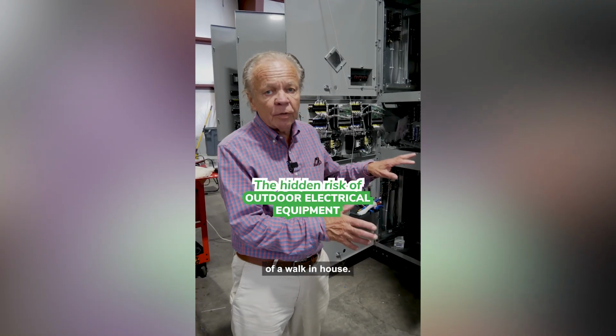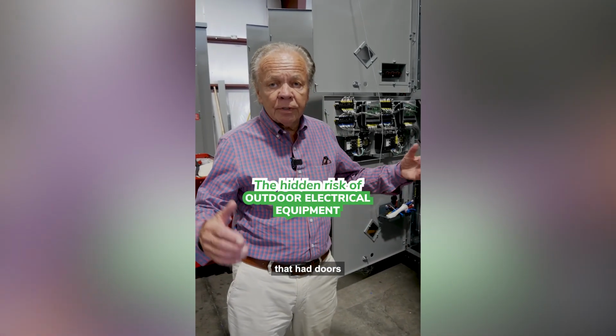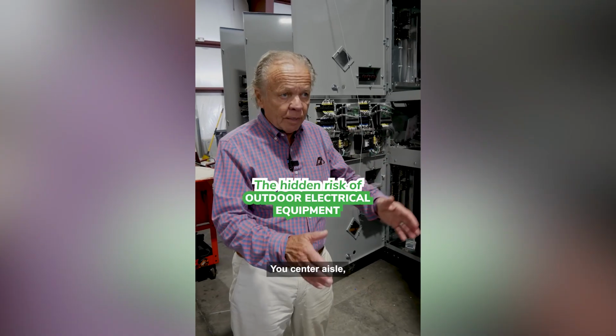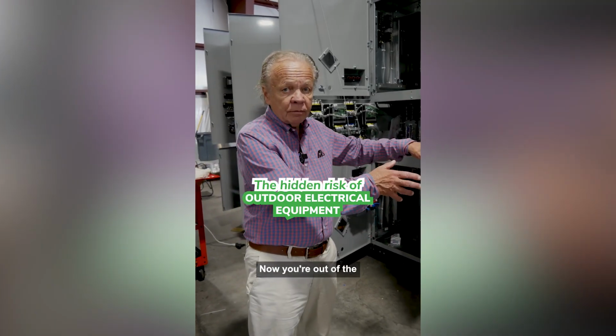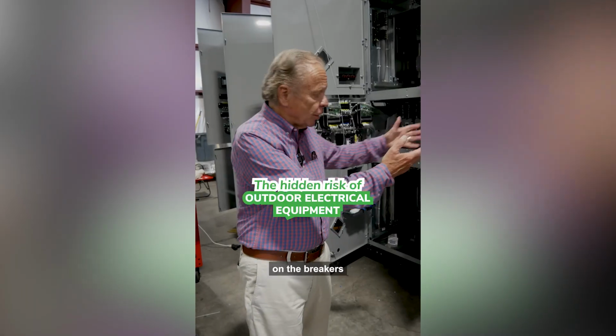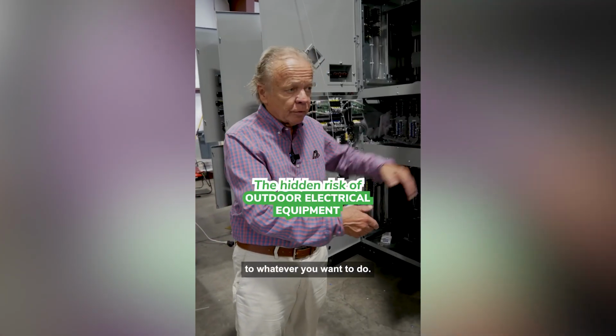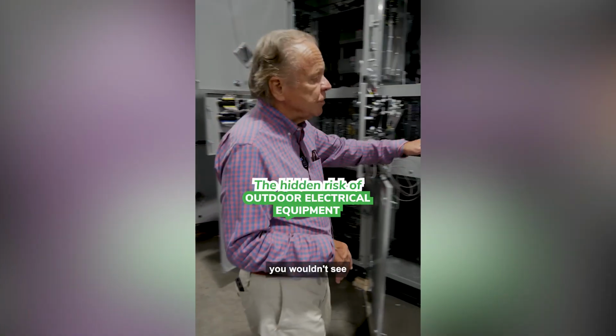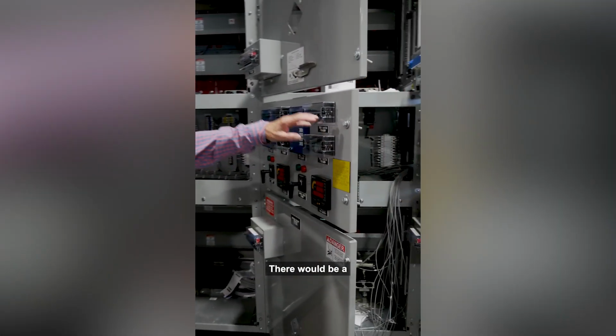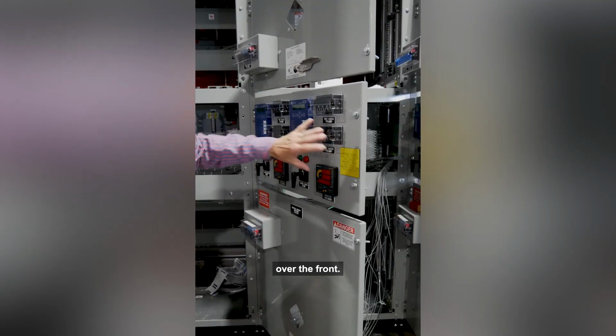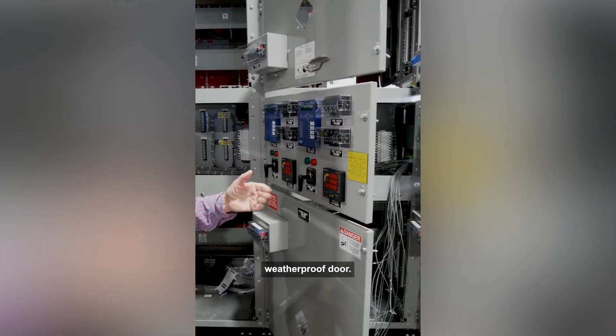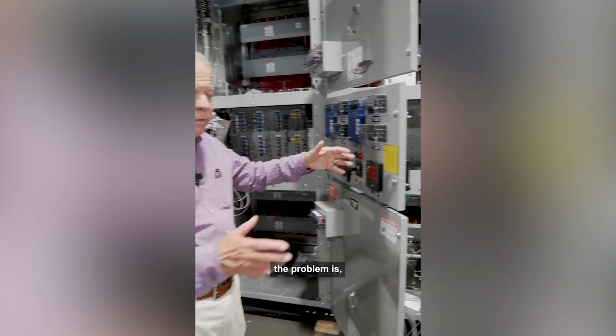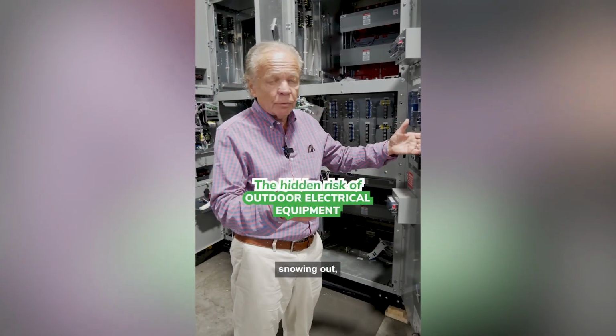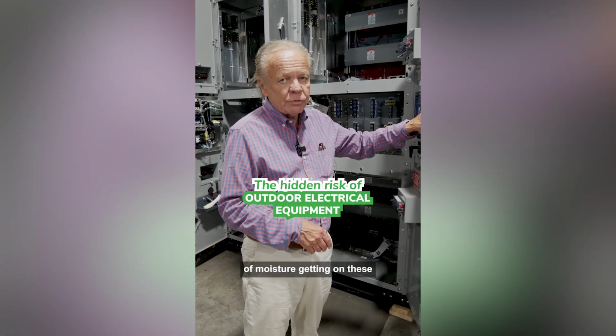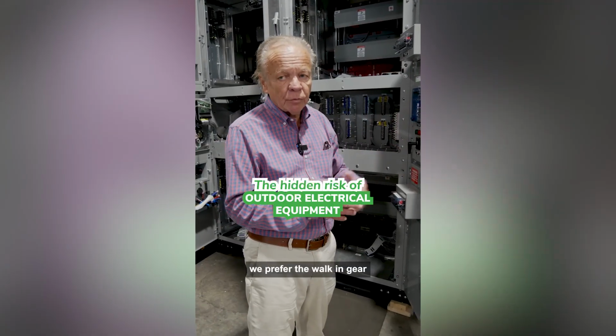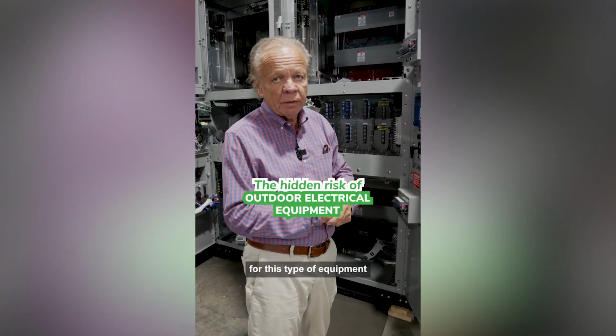This gear will go inside of a walk-in house. It's a structure that has doors on both ends and a center aisle you can walk in. Now you're out of the inclement weather and you're able to work on the breakers here, turn them on, turn them off, do whatever you want to do. If it was outdoor gear, you wouldn't see any of these. There would be a weatherproof door over the front. Typically the problem is, if you're outside and you open the door and it's raining or snowing, then you have a chance of moisture getting on these components. That's why we prefer the walk-in gear for this type of equipment with all the controls.